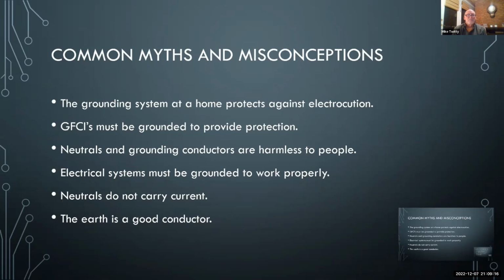Right. Okay, here's some common myths and misconceptions. The grounding system at home protects against electrocution. We just said it's basically there for power surges and lightning strikes. That's the grounding system. GFCIs must be grounded to provide protection. Well, if you've done many home inspections, you've seen a lot of GFCIs on older houses with no equipment grounds, and they work. They protect without being grounded. It's still not grounded, but they protect for shock. They're for electrocution protection, to protect people.